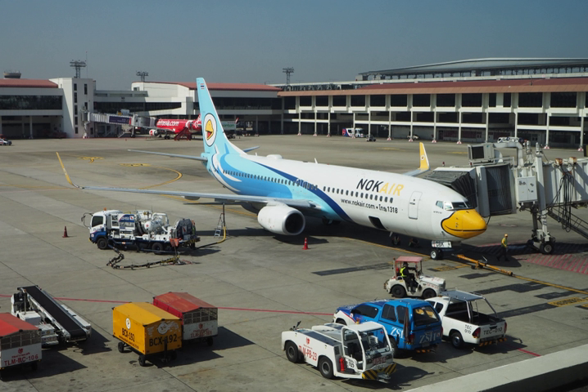The primary difference between Jet A and Jet A-1 is the lower freezing point of A-1. Jet A's freezing point is −40 degrees Celsius (−40 degrees Fahrenheit); Jet A-1's is −47 degrees Celsius. The other difference is the mandatory addition of an anti-static additive to Jet A-1. Jet A trucks, storage tanks, and plumbing that carry Jet A are marked with a black sticker with 'Jet A' in white printed on it, adjacent to another black stripe.